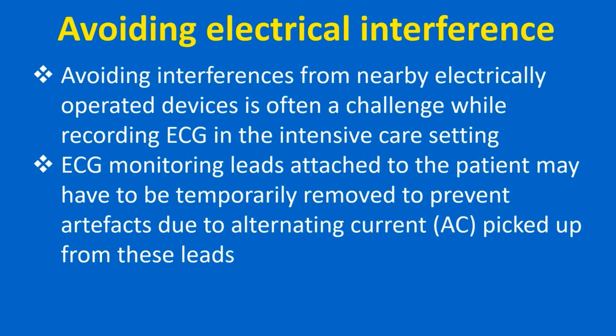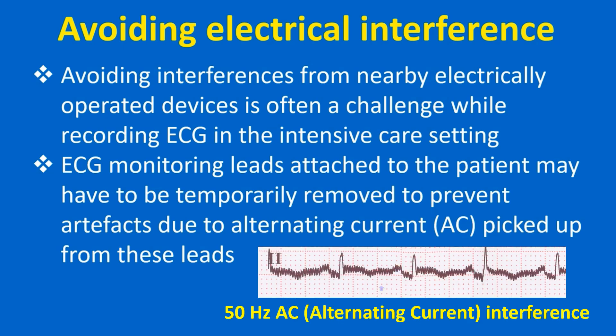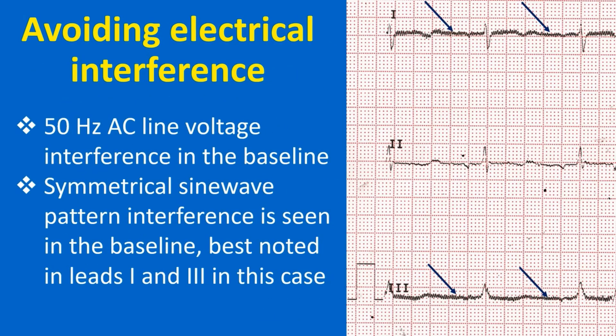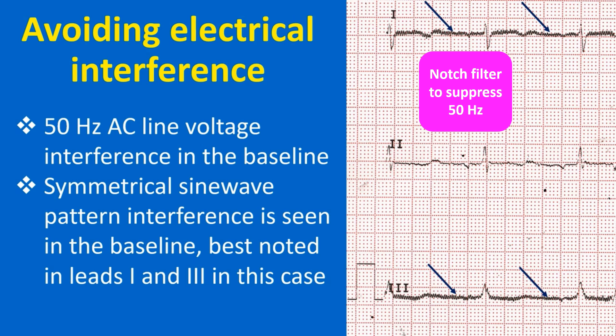Avoiding interference from nearby electrically operated devices is often a challenge while recording ECG in the intensive care setting. ECG monitoring leads may have to be temporarily removed to prevent artifacts due to alternating current picked up from these leads. Power cords of electrically operated beds, pneumatic compression devices, infusion pumps, and other devices in close vicinity may also have to be removed from power sockets to reduce electromagnetic interference from the AC line. AC interference is seen as a symmetrical sine wave pattern in the baseline at the frequency of the line voltage — either 50 Hz or 60 Hz. In most modern ECG machines, notch filters are used to suppress AC interference, though it may still appear if the interference is strong.